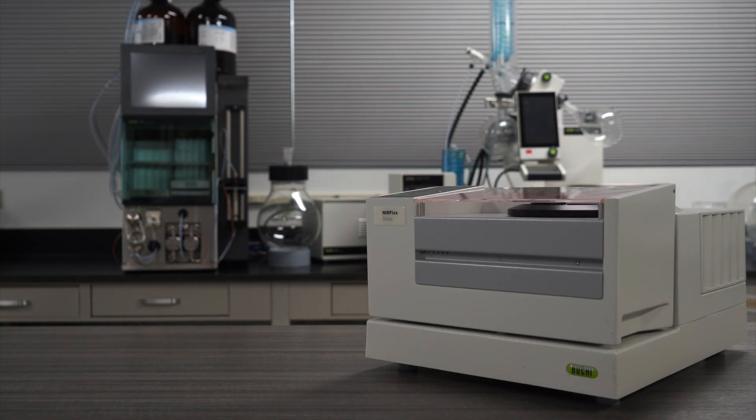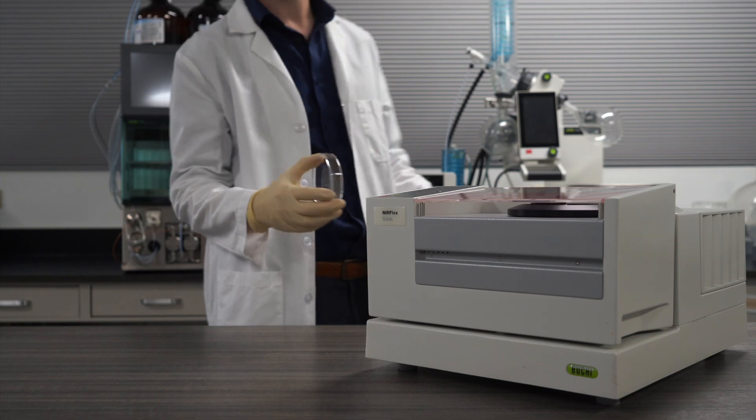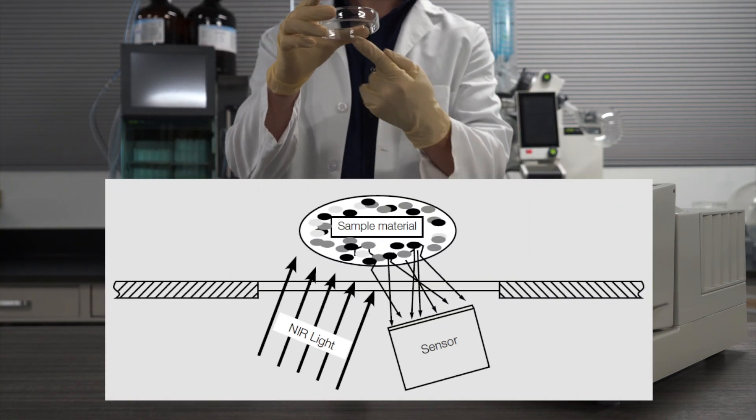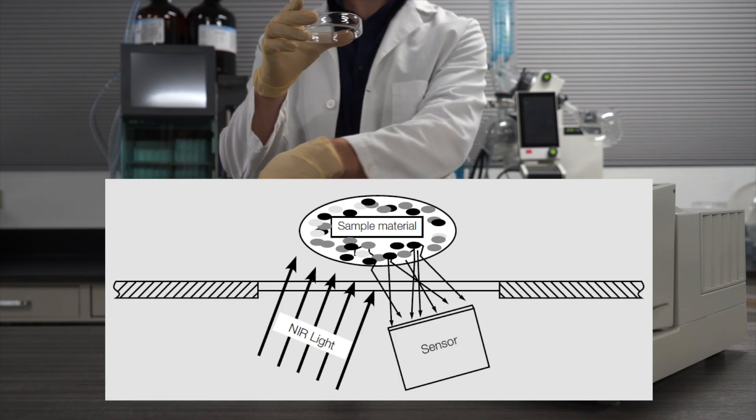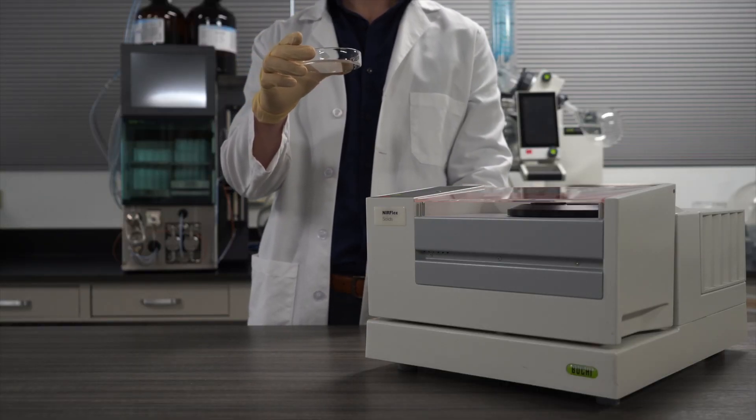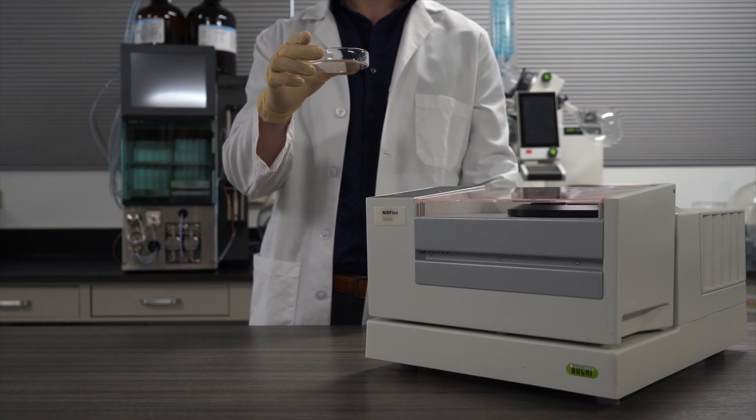With this module, we're working with diffuse reflectance. Simply put, the module works by directing light at the sample. The light gets scattered and absorbed by the sample, and some is reflected and captured by the detector. It is then processed and run through the calibration where it's turned into a sample measurement we care about, like sample identity.